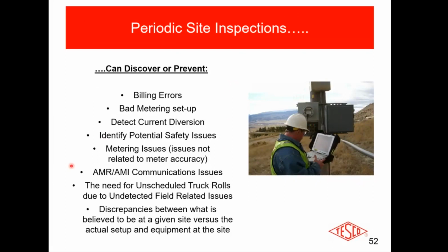All right. Okay, let's take a look here. I got a couple of questions. Patrick asks, are most of these items on a site verification checklist overlapping for checking high burden issues? I would think many of them could impact burden. There is an issue, and it would be a good place to start investigating. Absolutely. So when you do a burden test, you're actually checking the burden of the transformers. However, what you're not doing is checking the burden of the site. So to actually improve the burden on the site, you are taking the wires out, you're checking them for corrosion, you're cleaning them up, you're checking to make sure everything is tightened down.